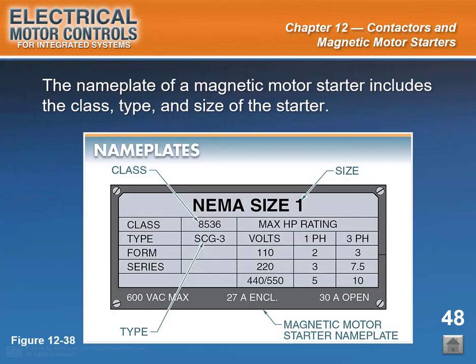Start of slide 48. Slide caption: the nameplate of a magnetic motor starter includes the class, type, and size of the starter. See figure 12-38. Overload heater coils for continuous duty motors are selected from manufacturer tables based on the motor nameplate full load current for maximum motor protection and compliance with section 430.32 of the NEC.